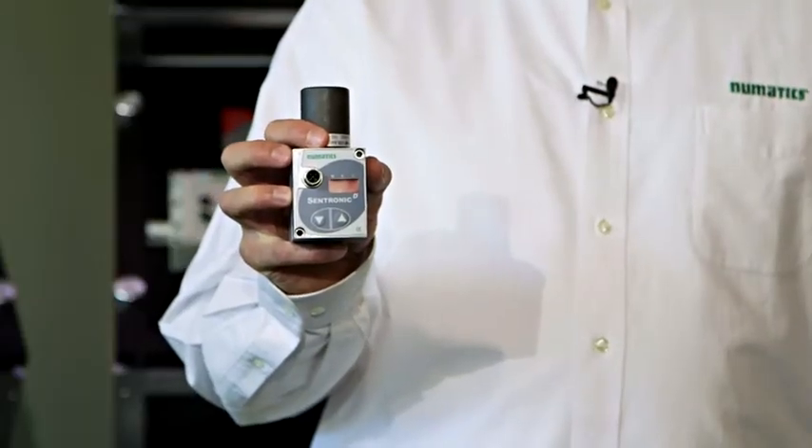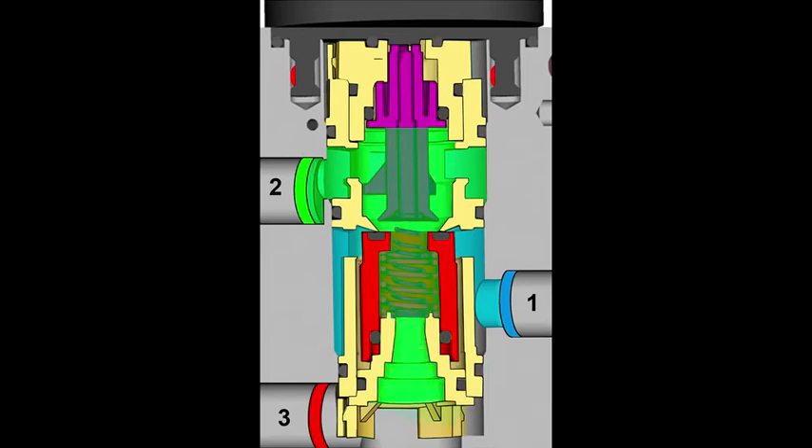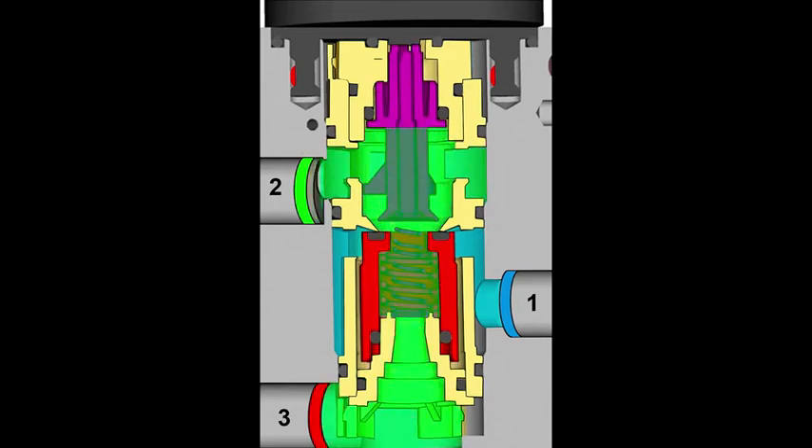This is Sentronic from Numatics. This unit uses a direct acting proportional coil to control output pressure. When you eliminate the wearable pilot valves and diaphragm, and instead vary current to a proportional coil, the end result is finer resolution and more consistent control right out of the box.